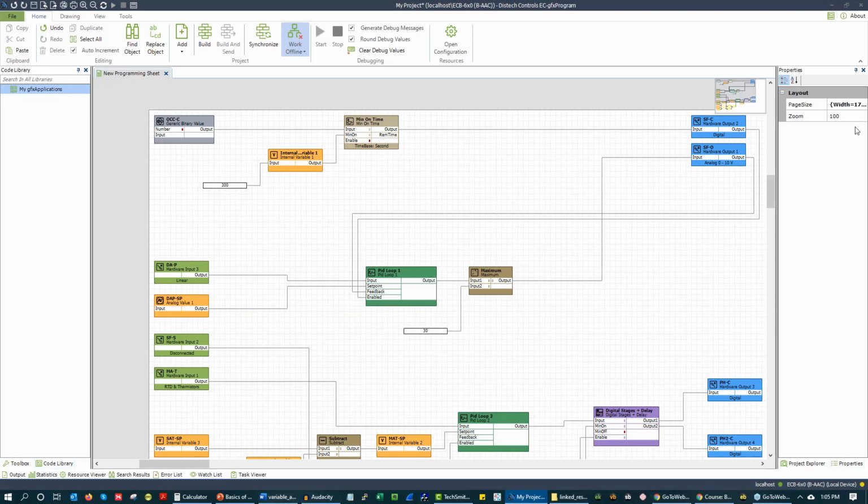So most of my time, whenever I'm working with another manufacturer's software, is purely just as I work through the program saying, okay, I need a min on block. In Niagara, it may just be called a timer block. In Distech, it's called a min on off or min timer, min on timer, whatever. In EasyIO, it may be called something different. And so it's just a matter of learning the names. So there you have it.